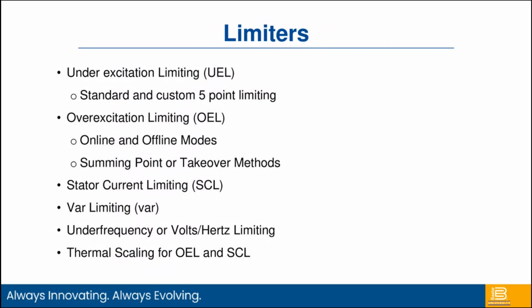One of the other advantages we have with the microprocessor is we can add a lot of additional functions. If we look back at the more complex old analog systems, we had a voltage regulator and then a series of black boxes. We may have had an over excitation limiter box, under excitation limiter, diode monitors, protective features, VAR power factor controllers. All those things were a separate black box in an older system. Now we're calculating all that. We have all the inputs into the digital voltage regulators, and we have a microprocessor which is capable of doing all that math, so we can implement all these additional functions.